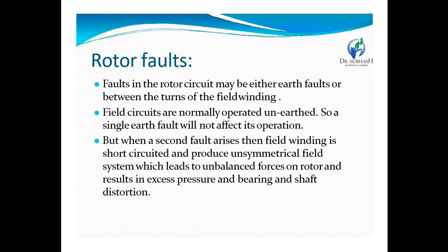Now rotor faults. We are clear about stator faults. Now the rotor may have a fault in the rotor circuit, and it may be either an earth fault or a fault between the turns. Field circuits are normally operated unearthed, so a single earth fault will not affect its operation.